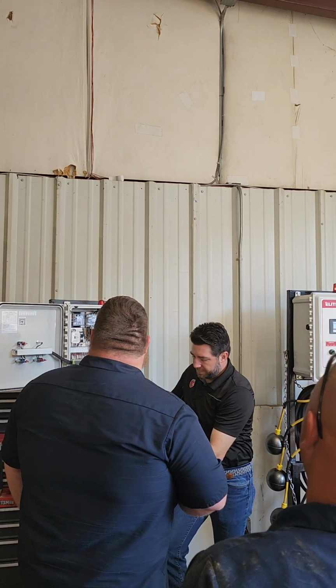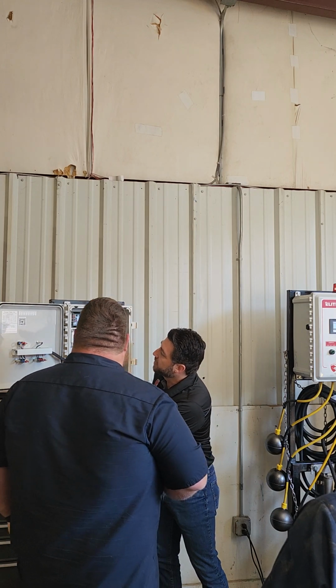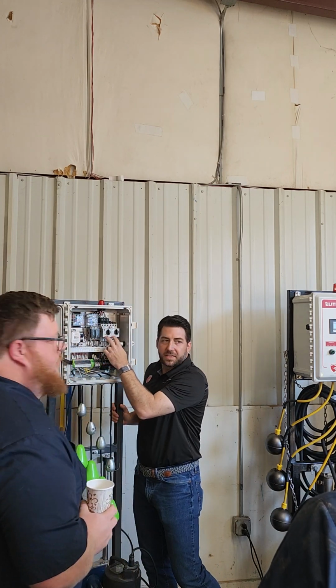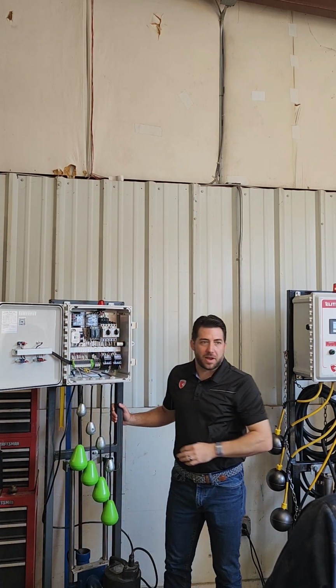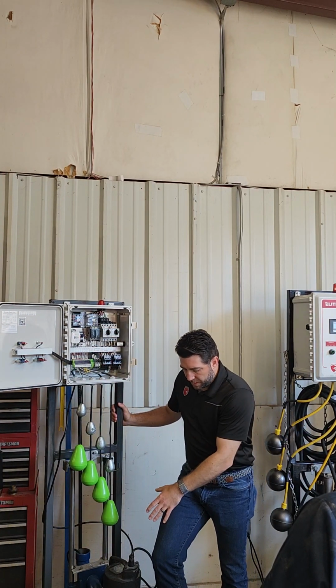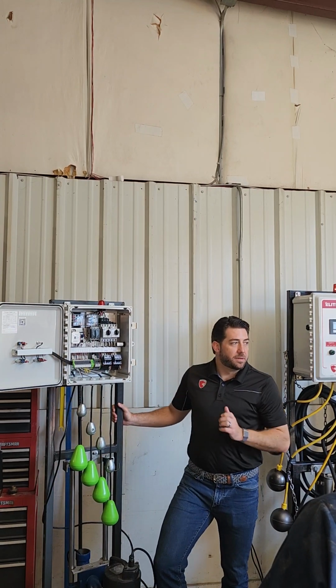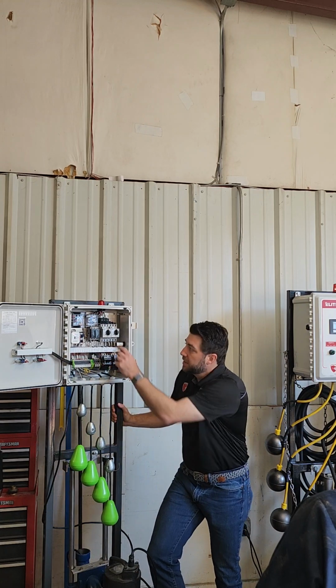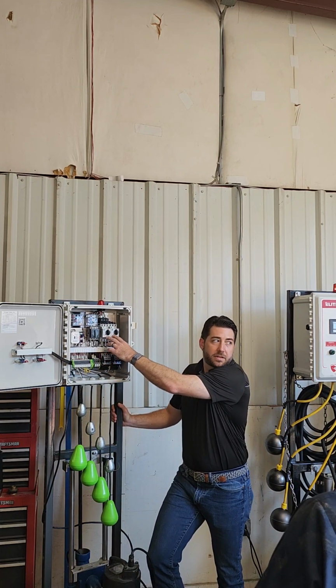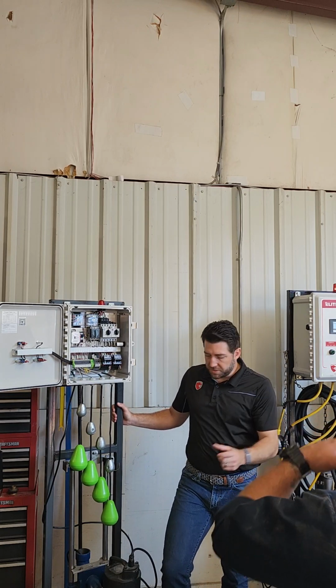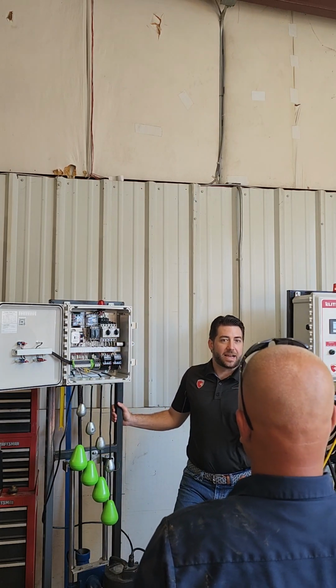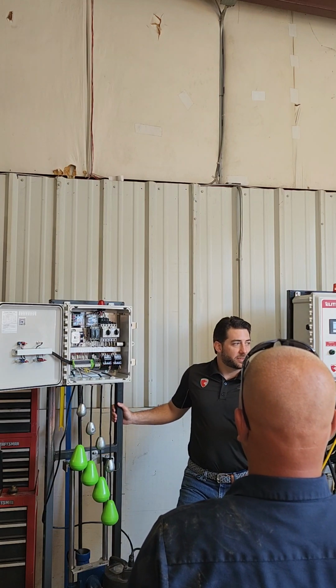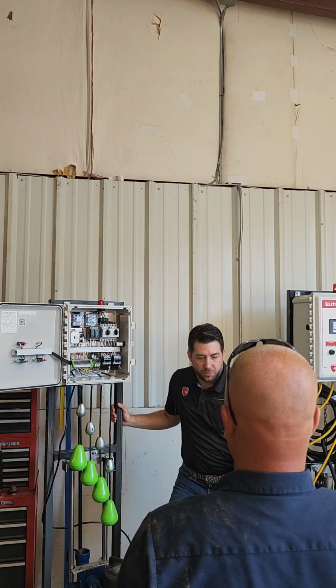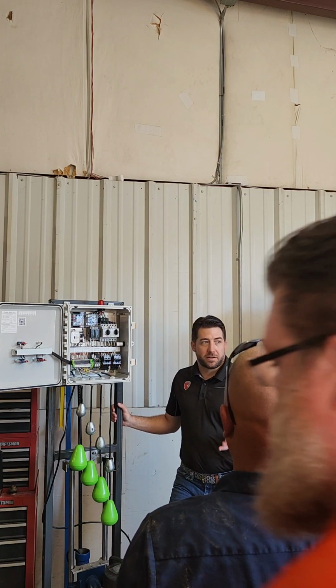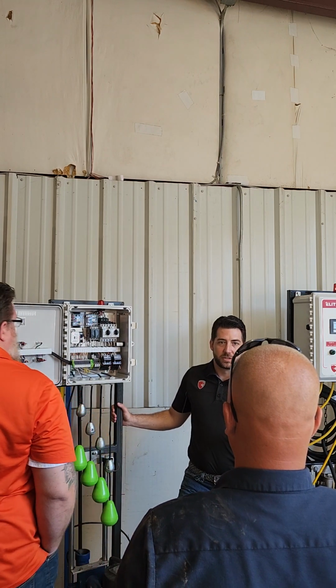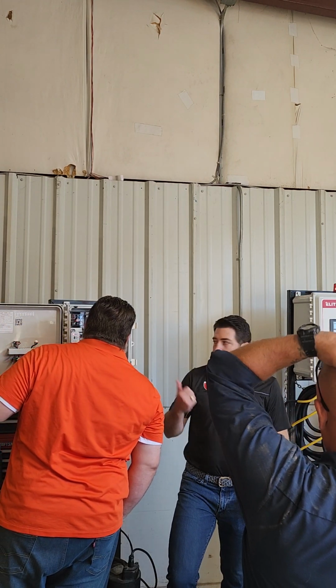So this pump doesn't match with this panel, I don't know that, but it actually ends up being the same range. So these types of overloads typically have a pretty tight range. So if you are changing pumps without changing a panel, you need to make sure that the new motor full load amps is within the range of the overloads. If not, you're gonna need to change out the overloads. Sometimes, especially in some ranges, they're really tight. They can almost be horsepower or pump specific. So you really got to make sure, because a 7.5 horsepower motor from Grundfos and from Myers or Wilo or whoever else may have different amp draws. So just because you're changing out like for like on horsepower, the amp draw may be different.